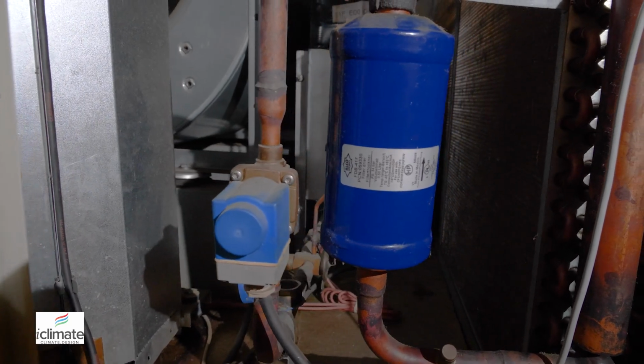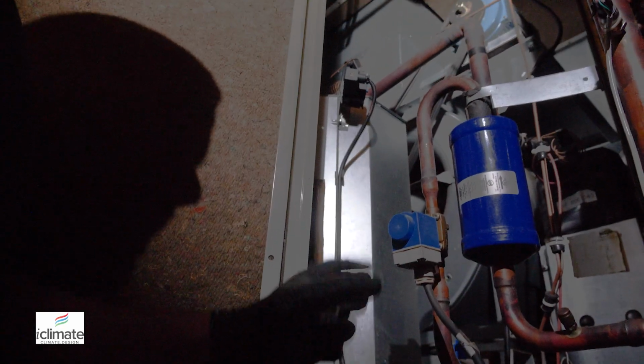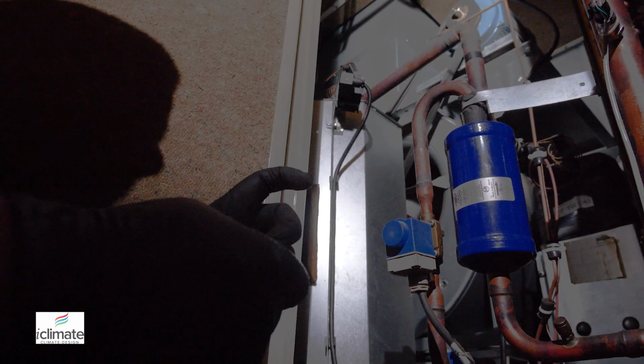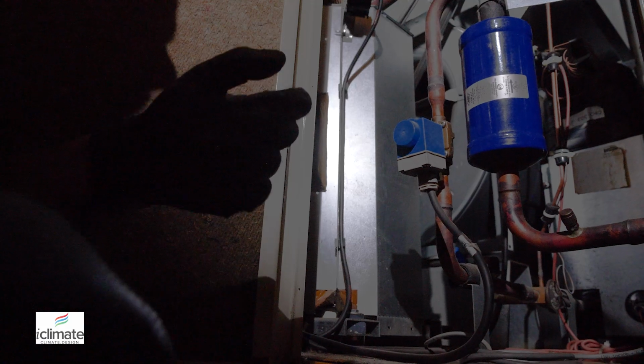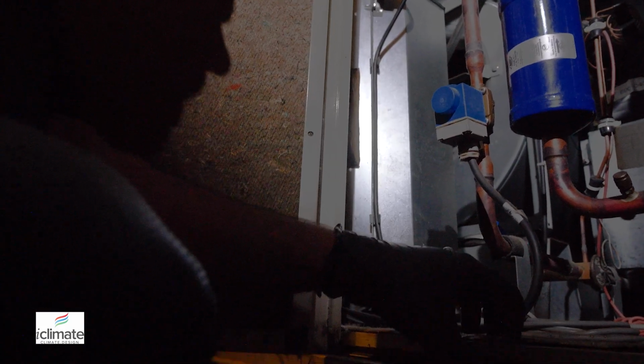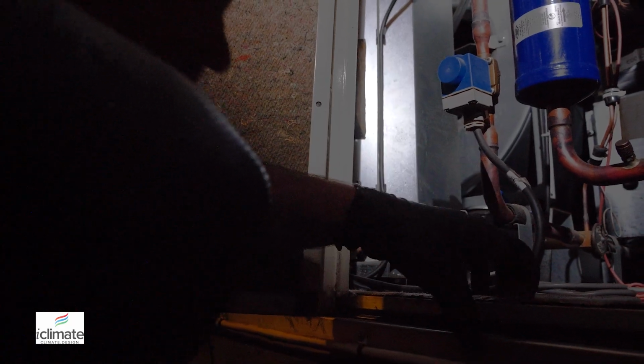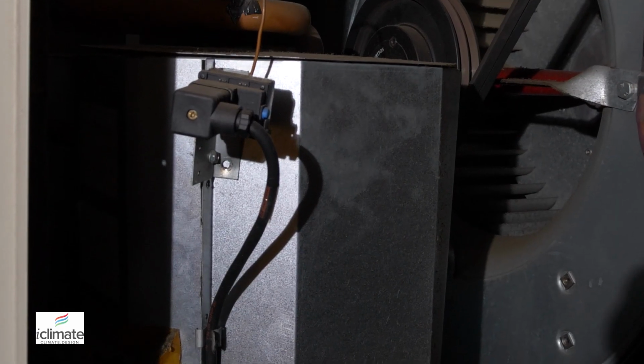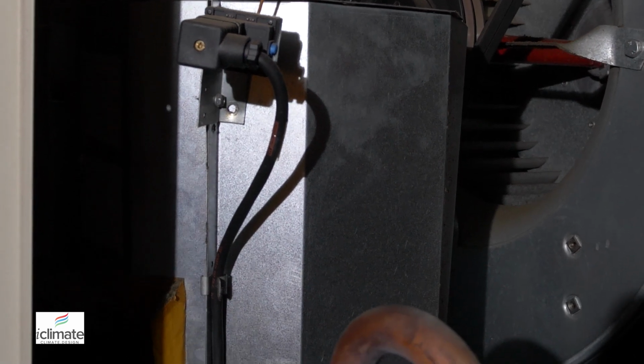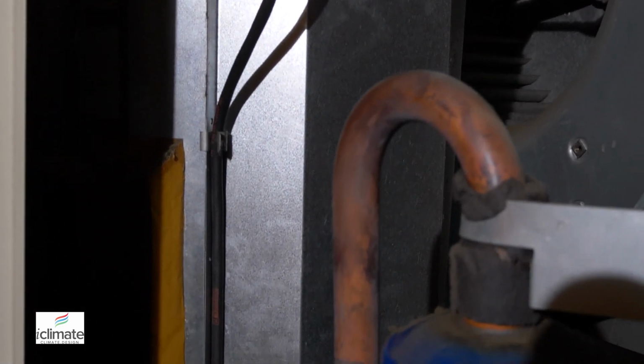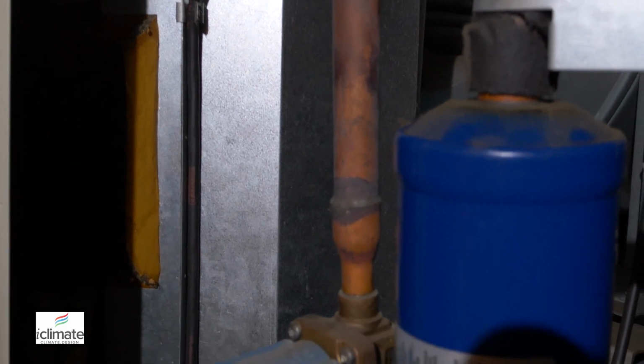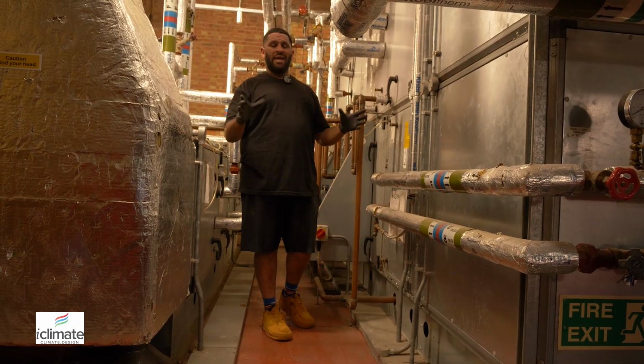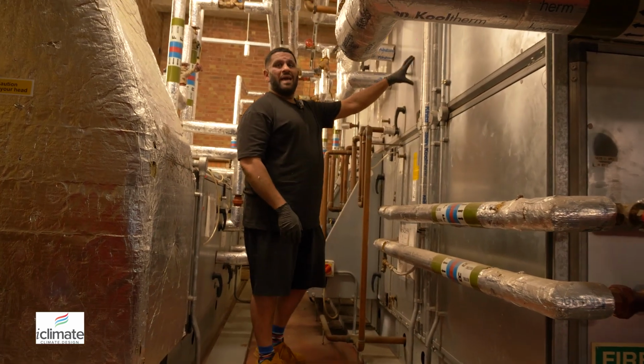This is obviously a large refrigeration system, so the motors have oil. What we do on a service is take the oil out and put it into an oil acid test kit, which gives us an indication of whether there's contamination or acid present within the oil, right? As soon as the oil is contaminated, like a car engine, that will affect the mechanical running and the clearances of the compressor. These chiller compressors are one of the most expensive refrigeration components to buy, and that's why clients always ensure that when they have the chiller under maintenance, it's done by specialists. Right guys, when I was talking about the AHUs earlier, this is what these are, air handling units.